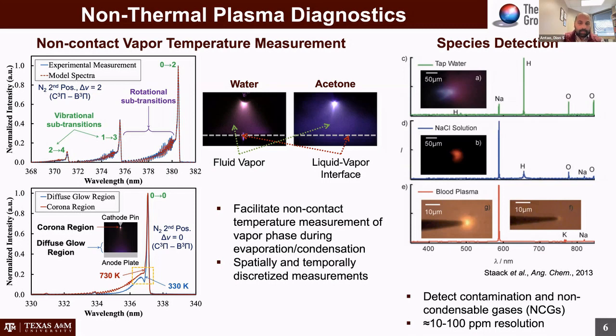So we do this microplasma-induced breakdown spectroscopy, in a sense, though not breakdown to the level you'd see in LIBS systems, where you actually damage the material you're measuring because LIBS makes a thermal plasma. Here, the non-thermal plasma is low enough energy that all you see is detection of species. By counting the photons through a spectrometer, say a photomultiplier tube, we can estimate the concentration of a particular element, molecule, or radical in the system emitting light.